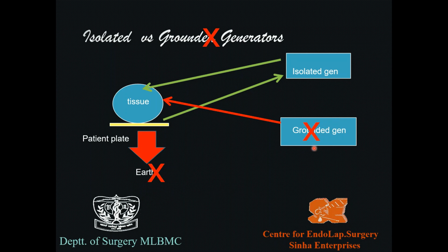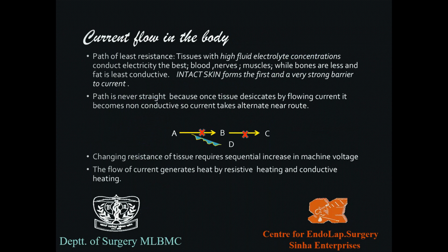What do we have? We have an isolated generator which sends the current and takes it back. And the patient plate would no longer be known as the earth plate. It will be known as a dispersive plate, right? So you know the difference between the isolated and the grounded generators. Now, having understood that, the current enters your body through the electrode. Where does it go, and how does it reach the dispersive plate? That is very, very important. It always takes the path of least resistance. We all know that electric current always takes the path of least resistance. Now, tissue with high fluid electrolyte concentrations conducts electricity the best.